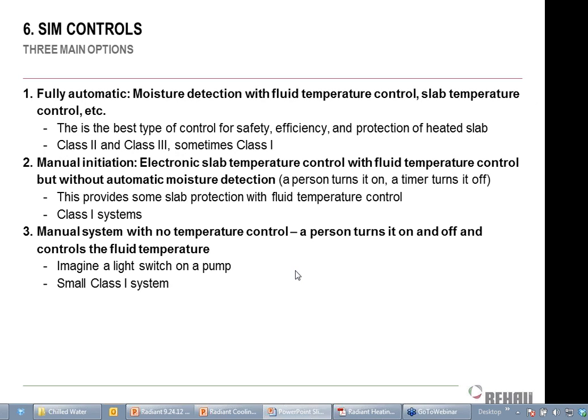But you also need to have safety controls on there, specifically a dew point sensor, to measure if I ever get below the dew point, I need to raise my chilled water temperature to keep it above the dew point by about 2 degrees. So that could be because of infiltration, but hopefully not, because these tend to go in systems that are well insulated and well sealed. But it could be because of infiltration, it could be because someone propped open a front door in a lobby, it could be because the window's open, it could be because the air handler failed. But whatever reason the dew point was allowed to get out of control, I've got to be able to reset the chilled water temperature to keep it above the dew point.